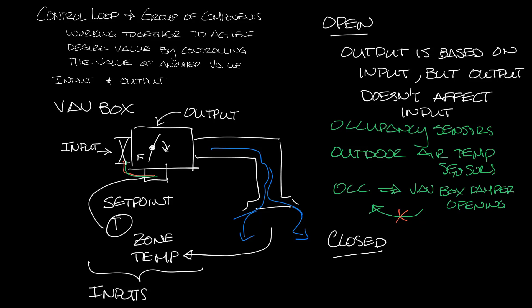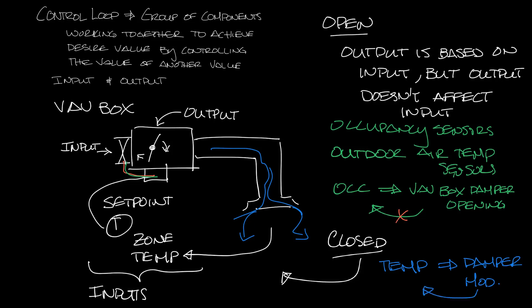So for a closed loop let's look at my example earlier. The space temperature and set point inputs tell the VAV box to modulate the damper and provide more or less airflow. The airflow changes the space temperature until the set point is met which changes the inputs to the control loop. So that's a closed loop.